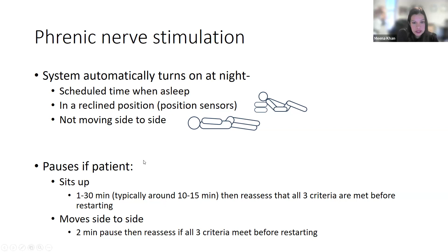So is it after the time that they're supposed to be asleep? Are they reclined? Are they not moving? And if all three are met, they'll resume. If the patient moves side to side, it will pause. We usually make this briefer, like around 2 or 3 minutes, and then it reassesses for all three criteria. And if the patient meets all three criteria, it will resume therapy. And then it turns off at a certain time in the morning that's preset into the device.